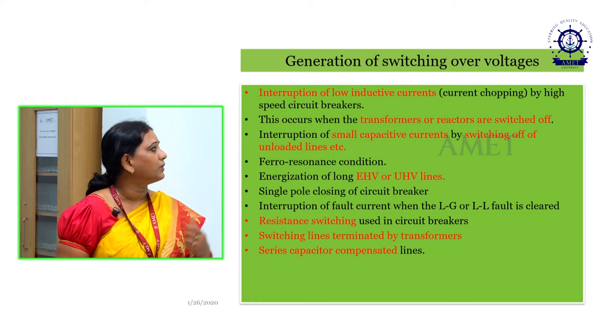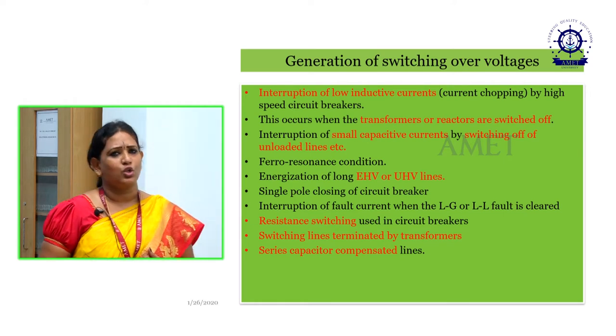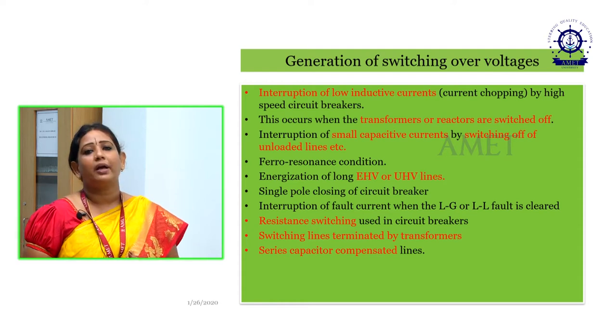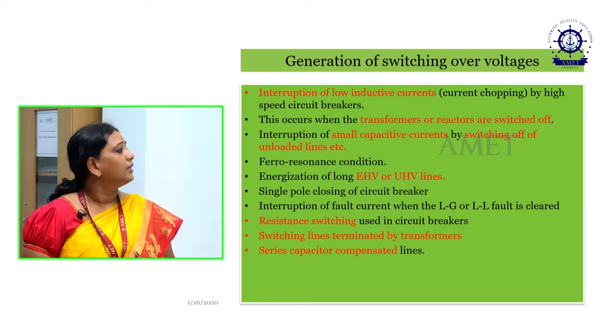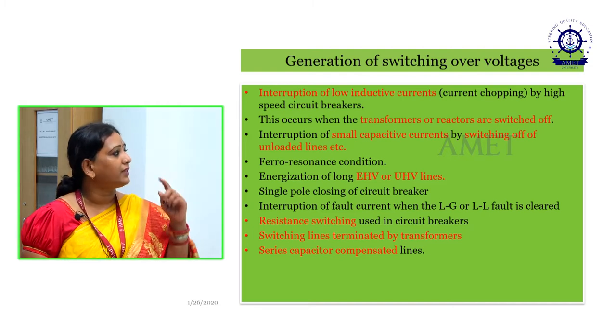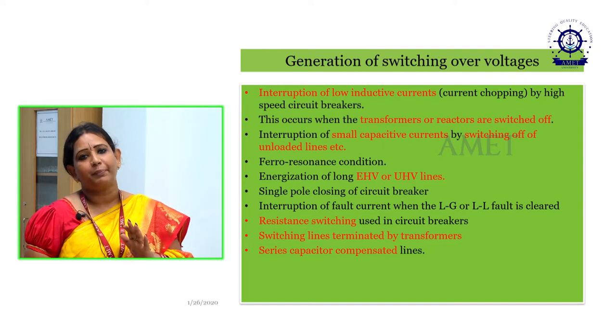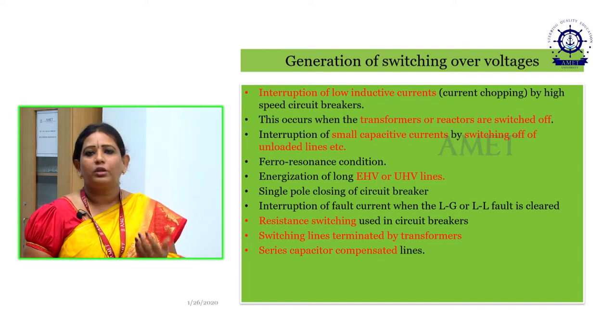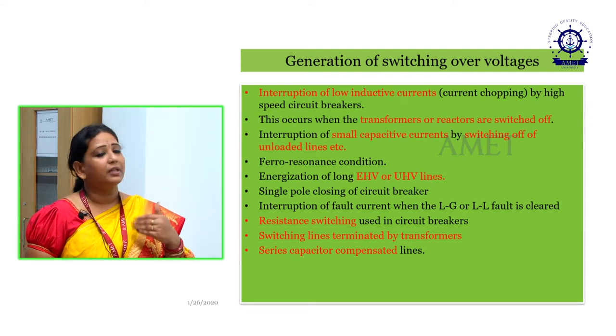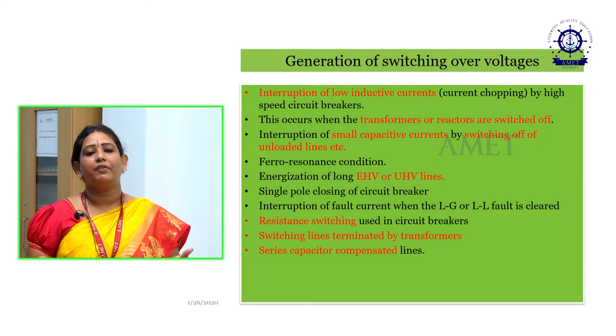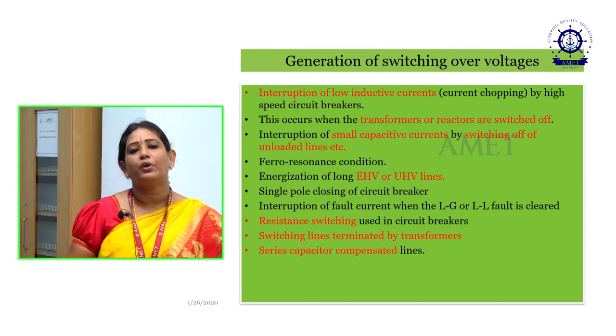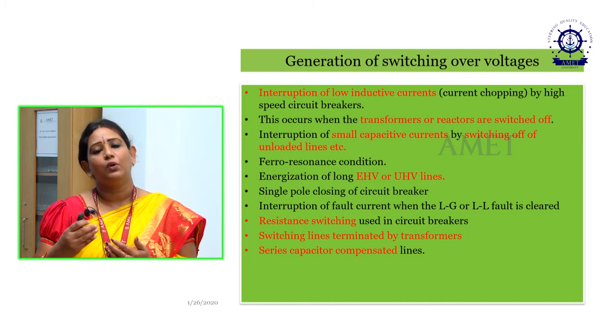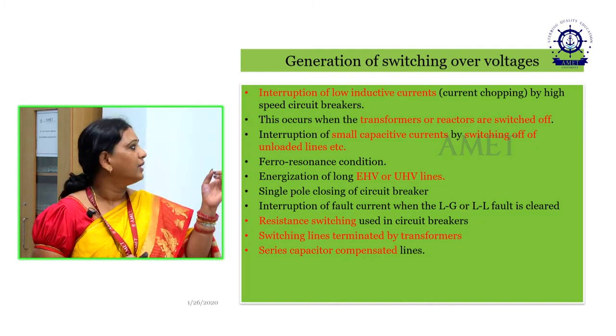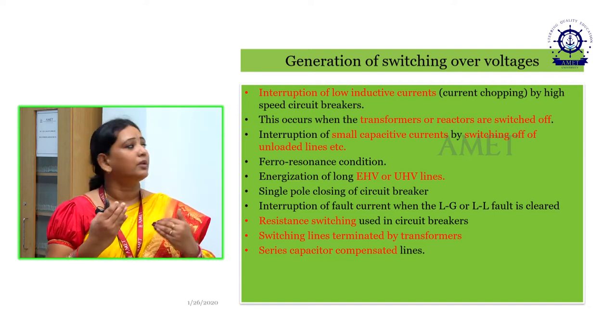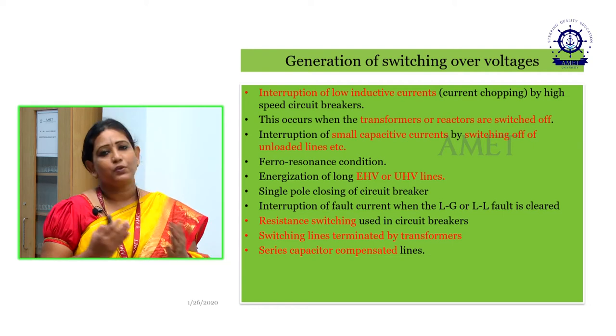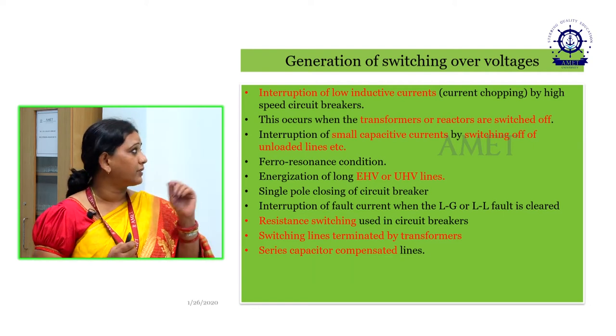Then next is the interruption of small capacitive currents, not only inductive currents. The same thing happens with small capacitive currents by switching off. The previous case was about forcibly interrupting, but the second case is about switching off unloaded lines. We know our transmission line has many loads. If it is overloaded, we can switch off or cut off some of the loads on the transmission line. During such conditions, the interruption occurs. We interrupt the capacitive currents by switching off the unloaded lines, and that in turn creates a switching over voltage.